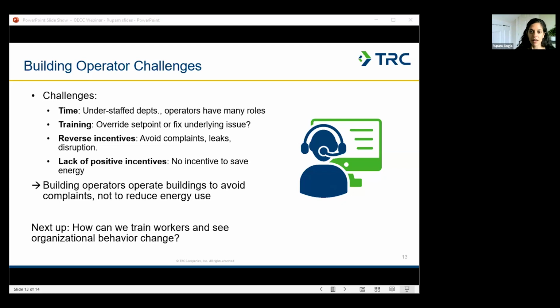Peter's actually going to talk about this one a little later, but building operators are often not trained sufficiently to know how to fix the underlying issue when there's a problem. So the easiest, most expedient thing for them to do is to override a set point or apply some other manual control. That's really how we end up seeing things like supply water temperatures being much higher than they needed to be - that may have been an operator thinking that was the easiest way to address an issue.